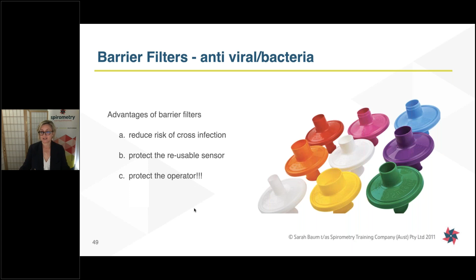So what we recommend is documenting the date that you start using filters in your maintenance logbooks, and that should be something you've got with your spirometers. If this is something you're going to do permanently, make sure your procedures manual reflects that this is a common step in taking your spirometry measurements.